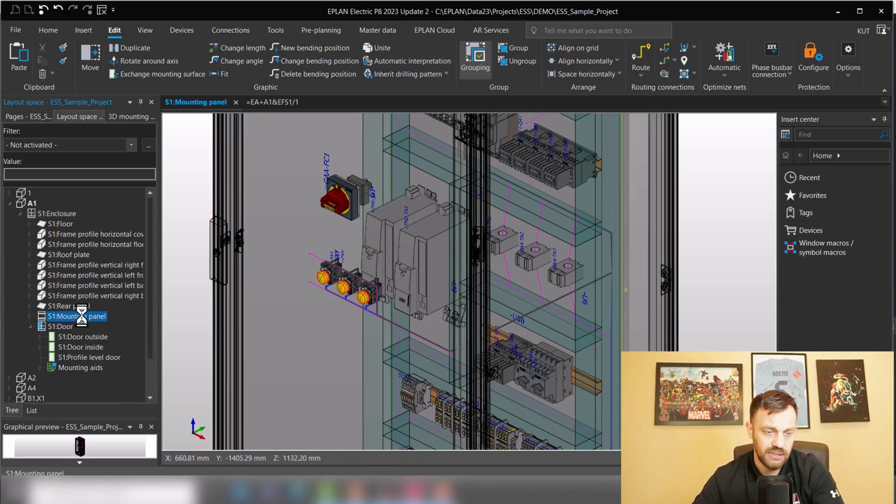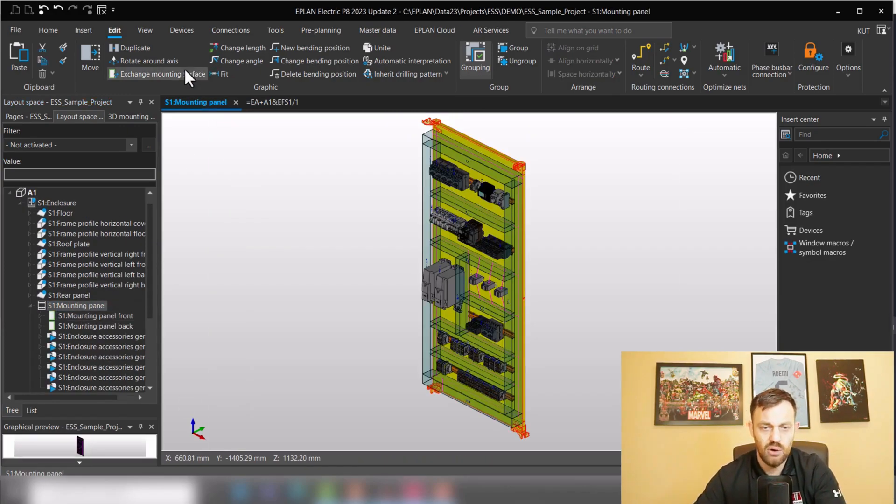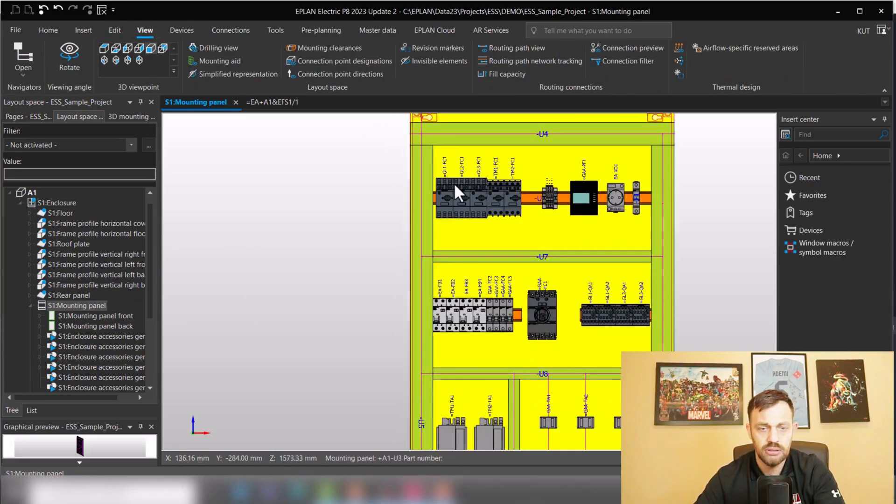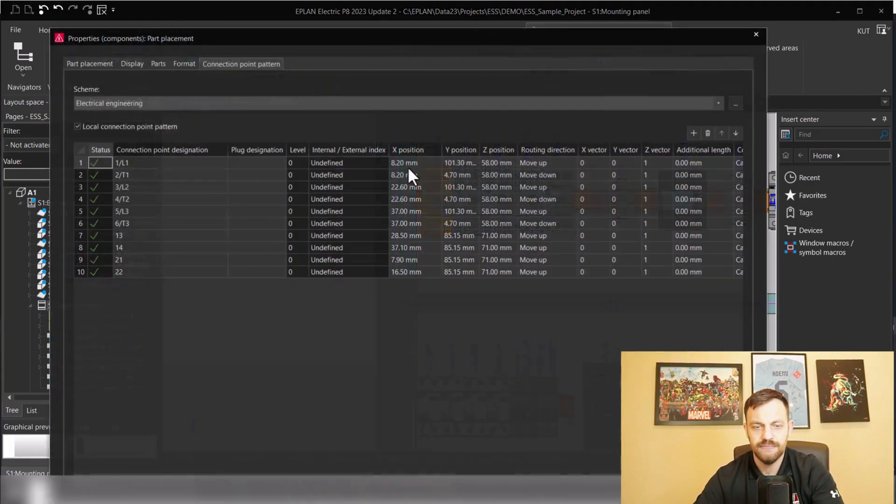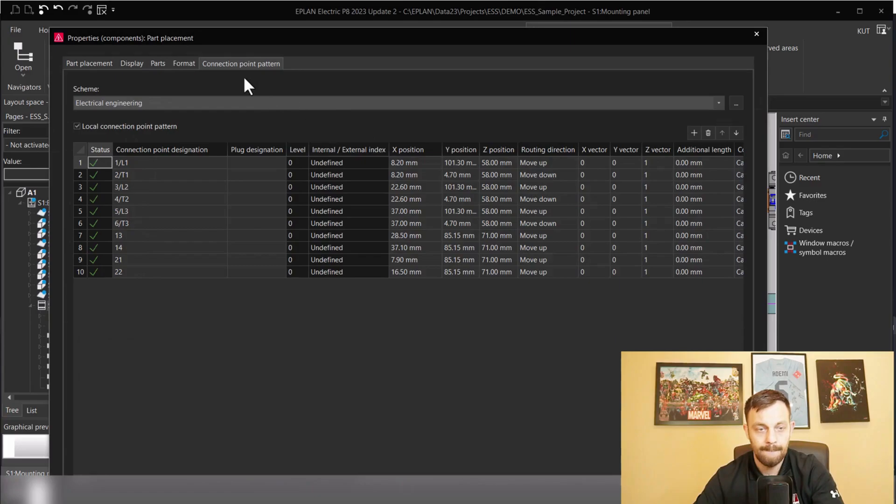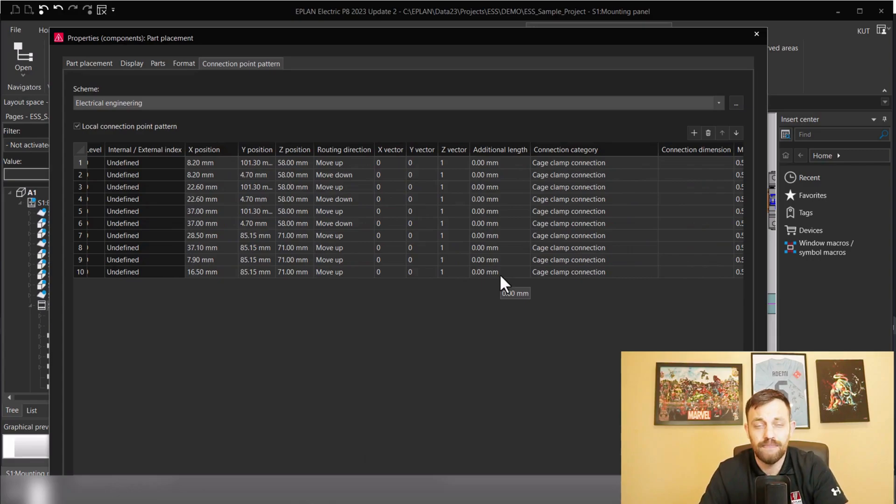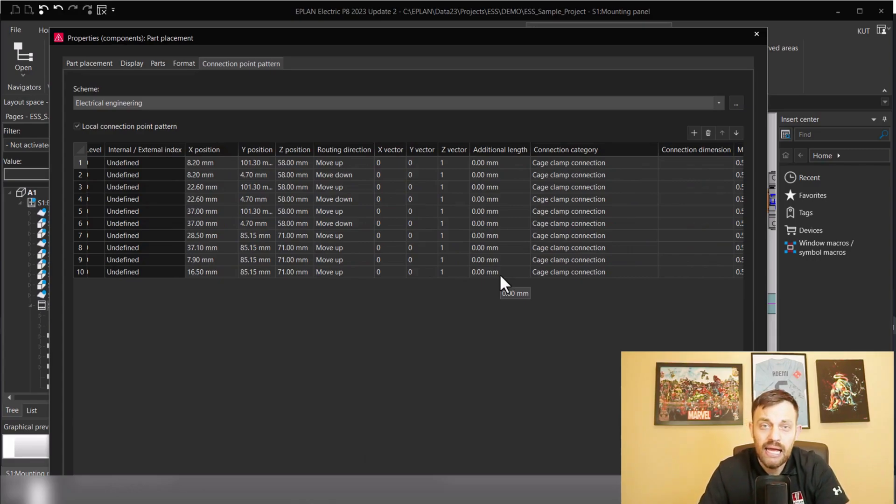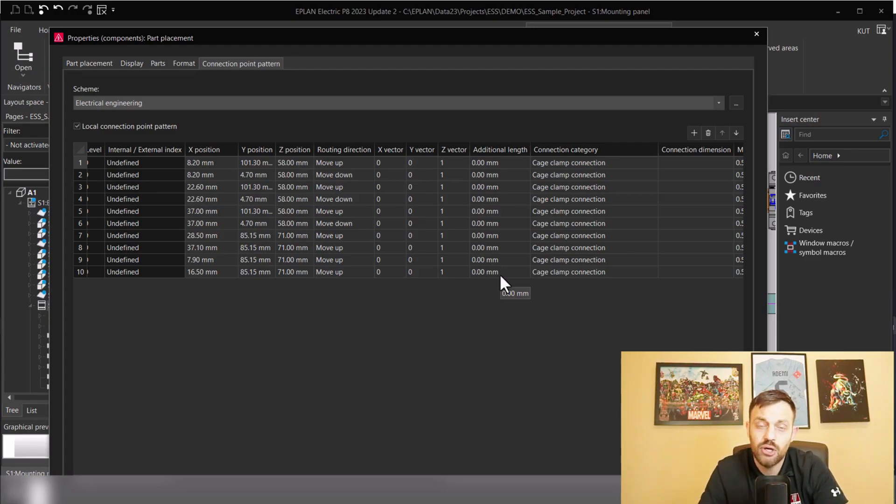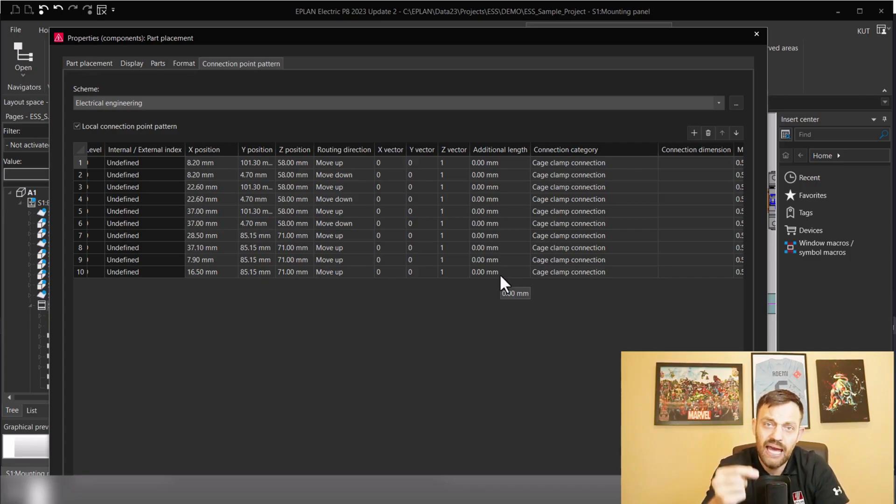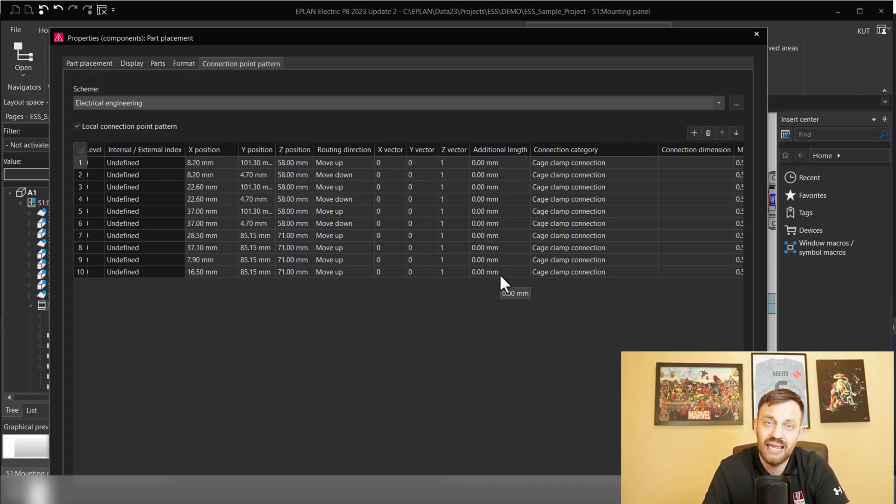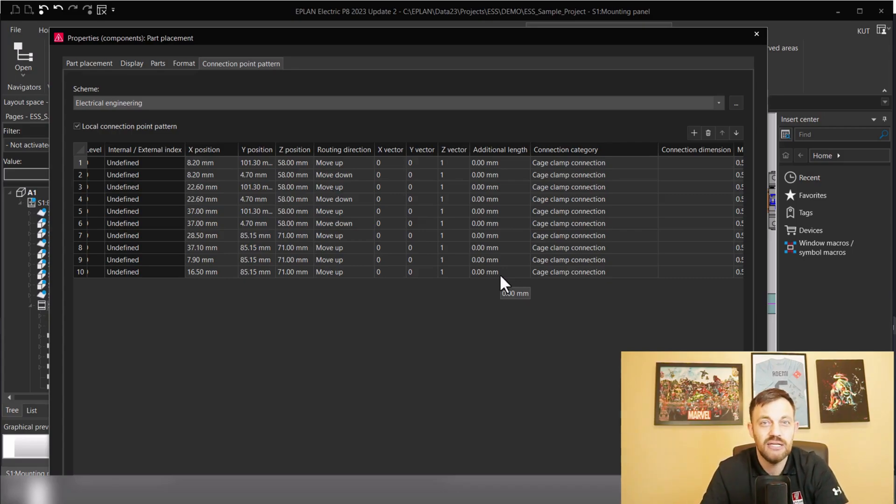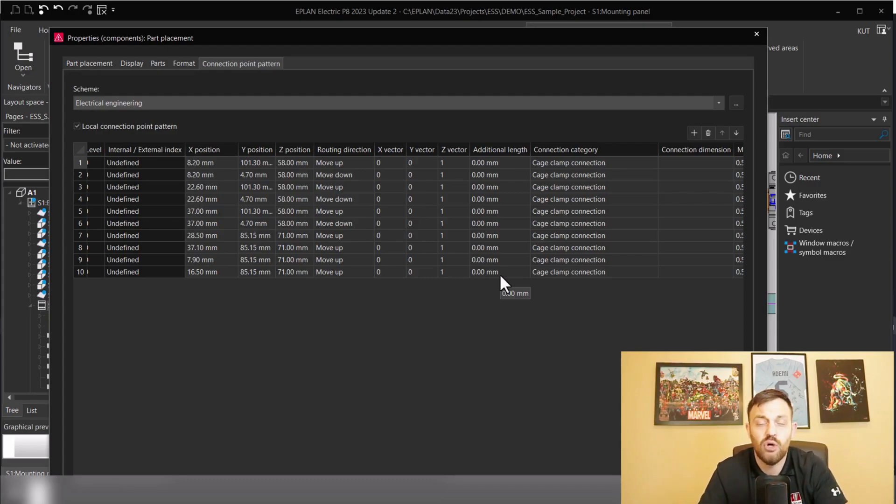The first step will be on the component level. You could select the device, and under connection point pattern, you have the functionality to add additional length. Where is this useful? This is useful if you define the connection point pattern but don't know the exact position of the wire termination point and would like to add additional length to make sure that when the wire lands on the device, it gets, for instance, additional 10 millimeters or 15 millimeters to make sure that the wire is long enough on the device perspective.